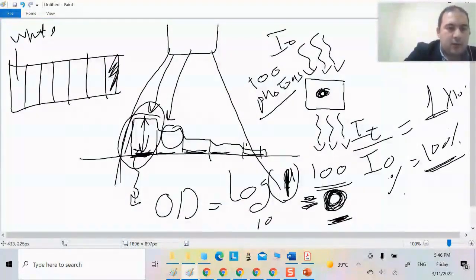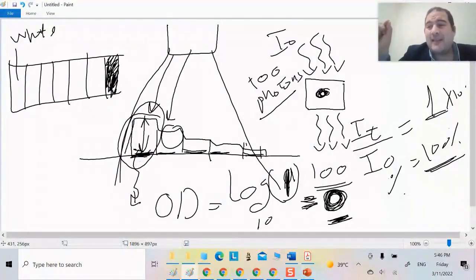At some point, when it reaches the black, it starts using a specialized device known as a densitometer. Note carefully that there is something called a sensitometer, which is used for the calibration curve. As for calculating optical density, that's done with the densitometer. As I previously mentioned, I take the film and see how much it burned in terms of darkening, and the same story applies here.